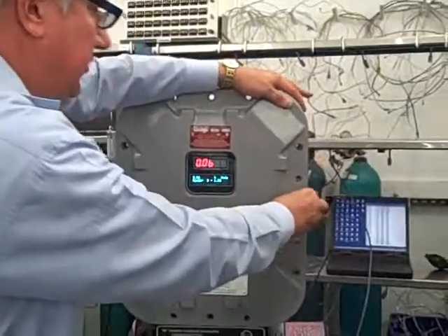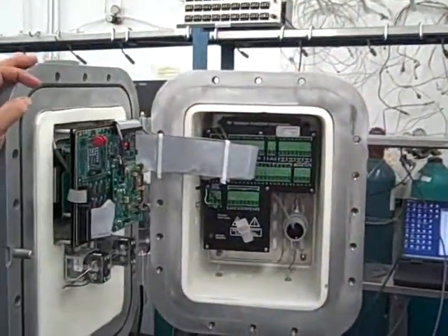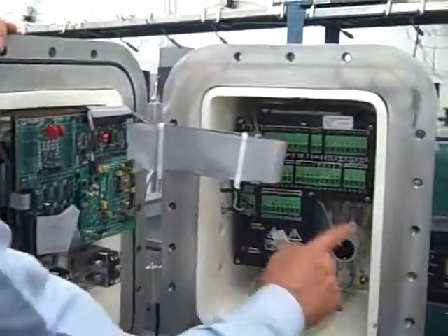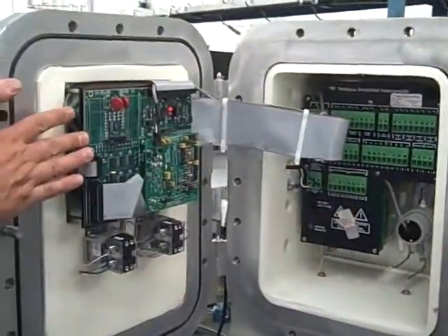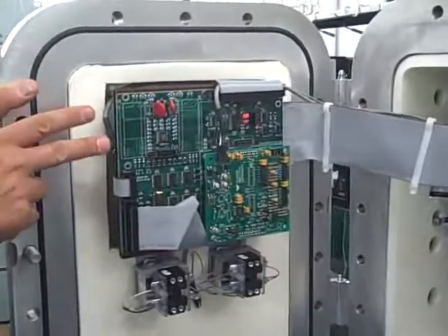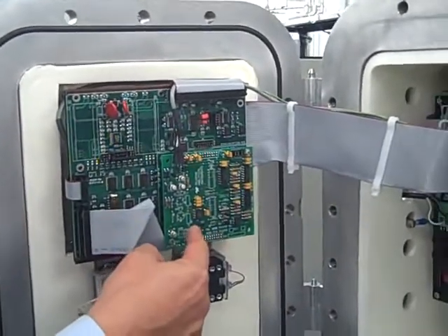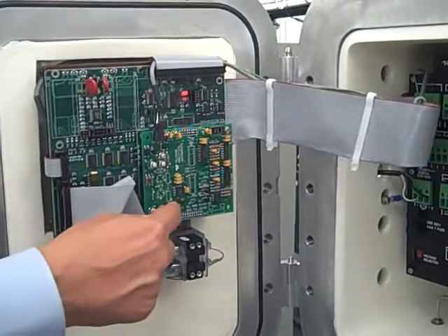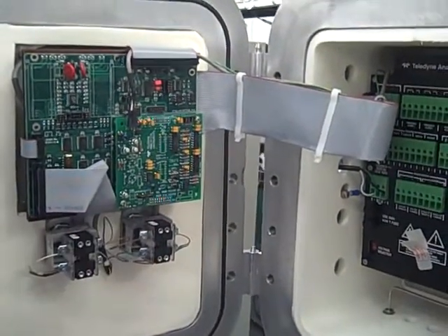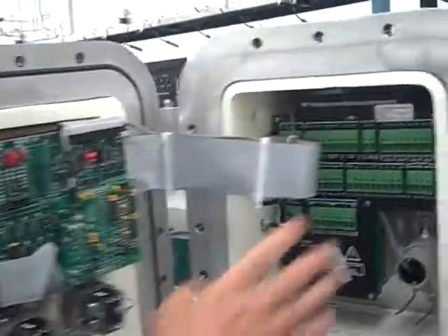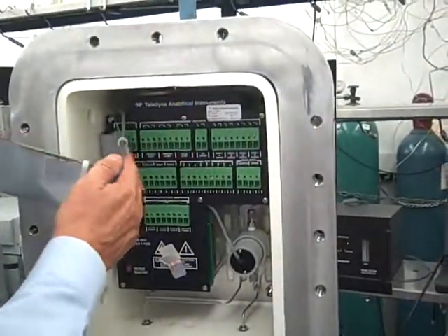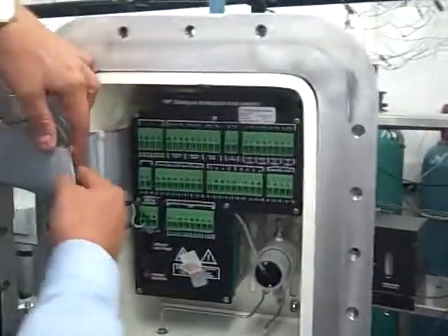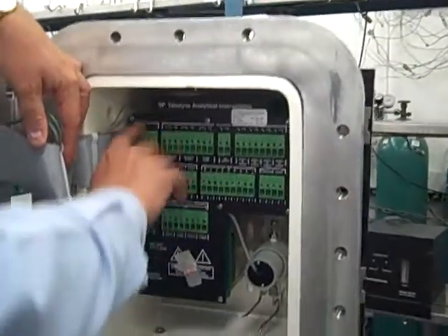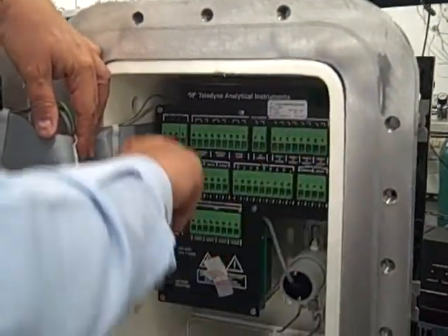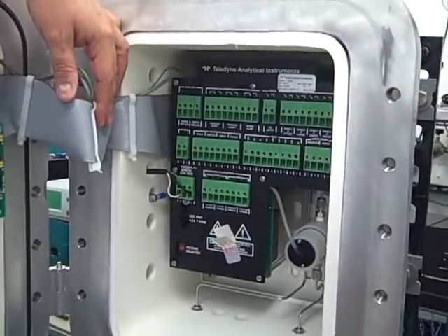So first of all, let's take a look inside this unit. Again, both the 3020P and T have identical construction with the exception of the sensor. This is the motherboard, the computer board of the unit, that contains a microcontroller. This is the preamp board that processes the sensor's output signal, which in this case is a current, and converts that to an oxygen reading, which we then show on the display. This is the power supply board and interconnection board, and this is of particular interest for our customers' technicians, because this is where you will make your connections to your process control system.